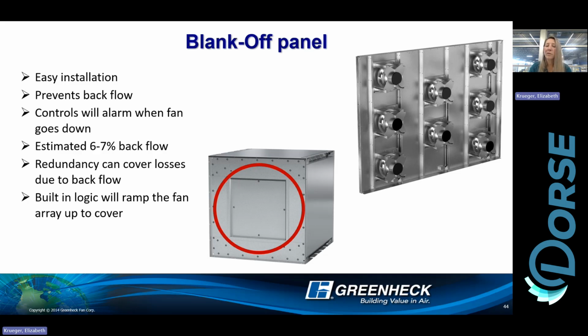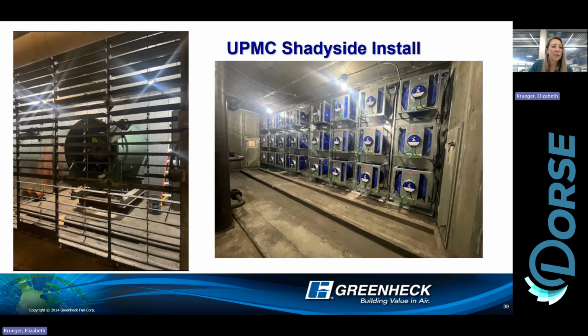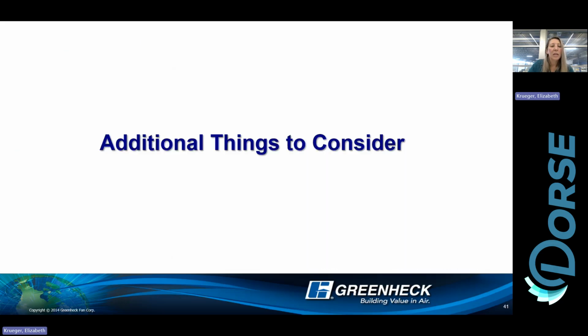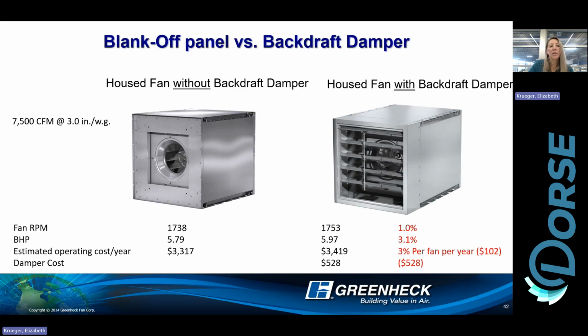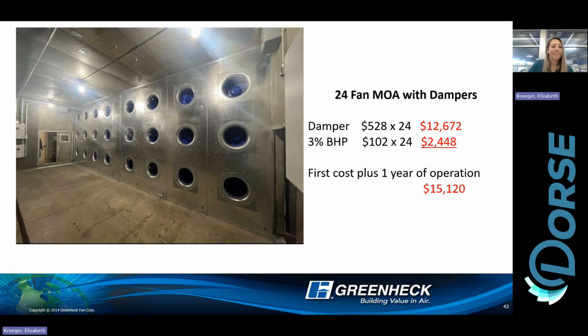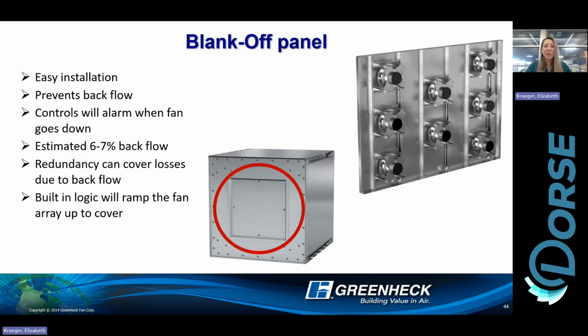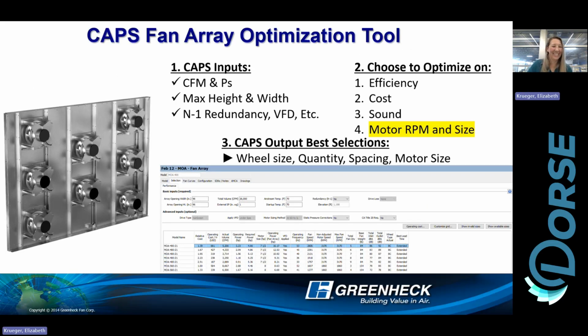I know sometimes you're just going to have dampers, especially if you're going to shut down the whole system. That's fine. You can put a damper wall in. Obviously, some of our applications have louvers, and these could be damper walls. But really, in front of each fan, we don't need a damper. That's my soapbox on that one.